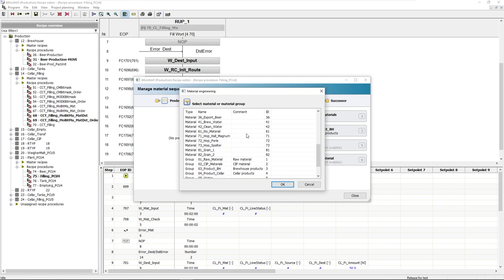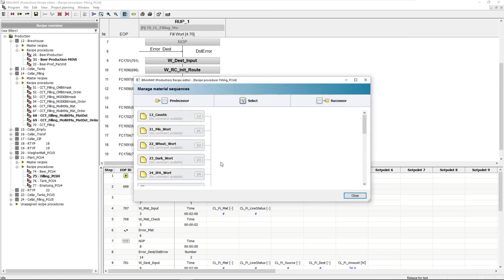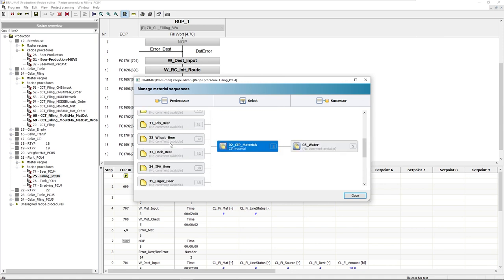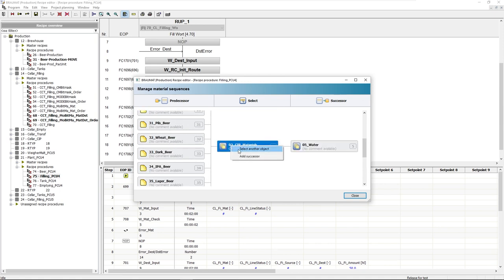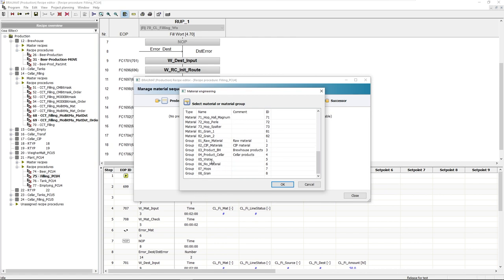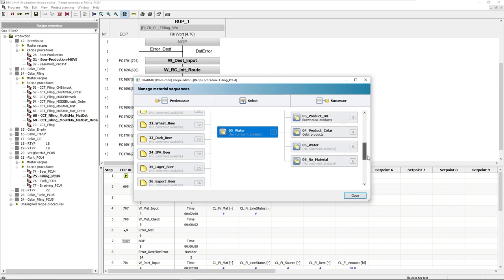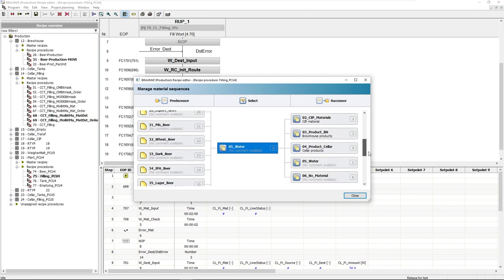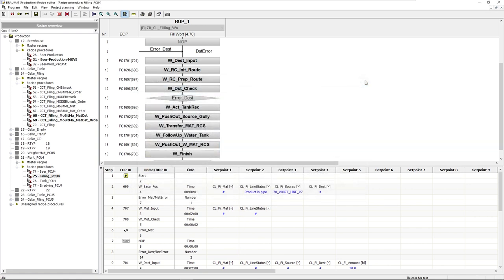If for instance we take a look at the most critical materials, CIP material, then in my example I only allow water, brewing water or cleaning water. Whatever comes before, and this rule is then created automatically, is of no relevance in this case. My least critical material would be water. This is a rule that the Braumat system will generate for me based on the other rules I entered earlier. In other words, before and after water, anything is generally allowed.